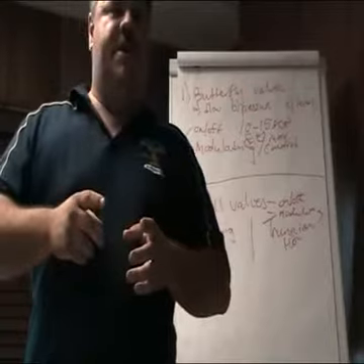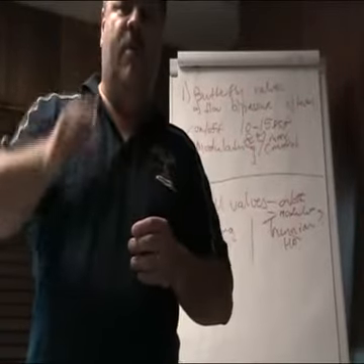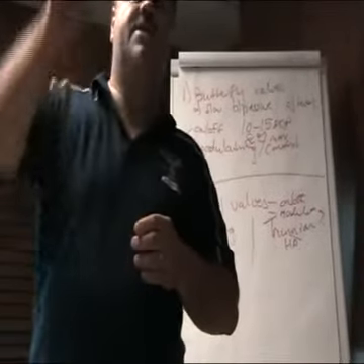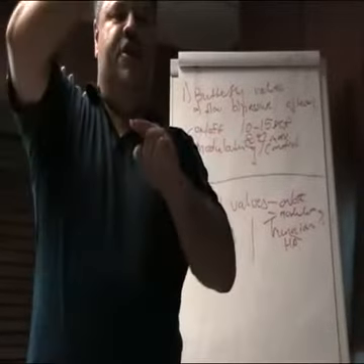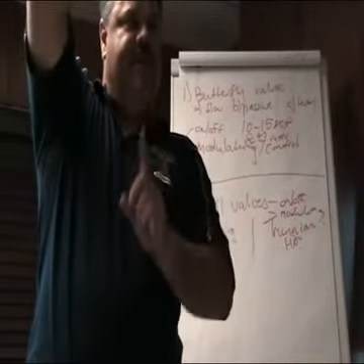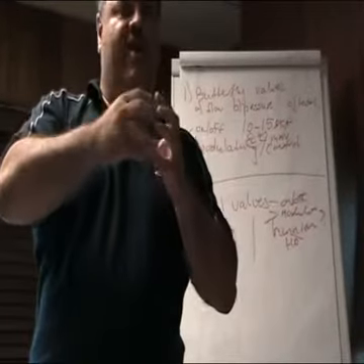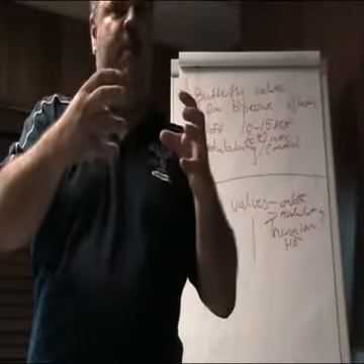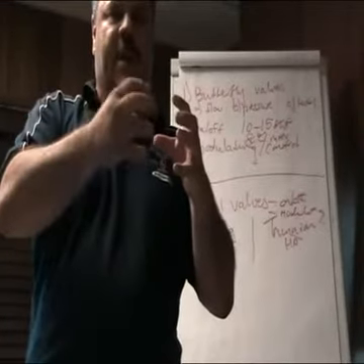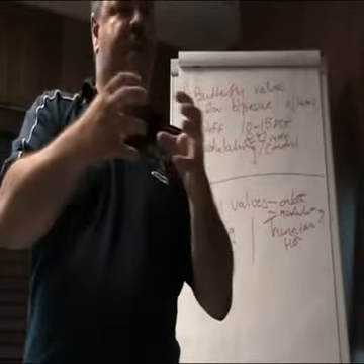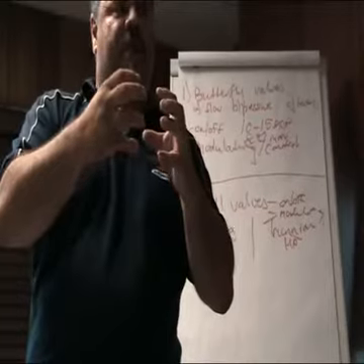The difference is, on a floating ball valve, you can't see the ball now, but we'll send the ball around, the ball inside that valve is not supported on top or bottom. They call it a floating ball valve because there are two seats which it is sealing against. So this little ball is floating between these two seats. But it's for low pressures.